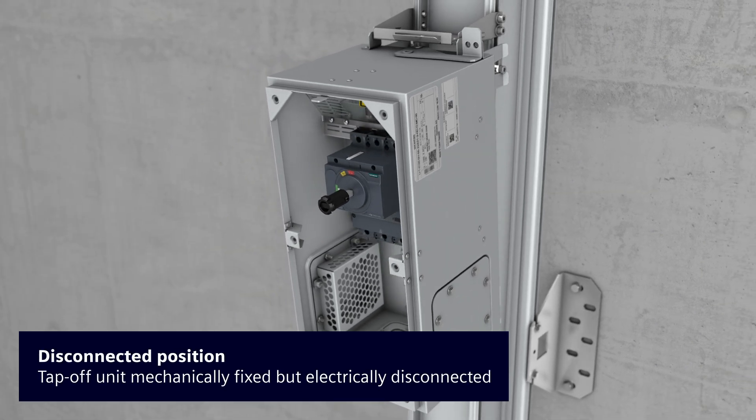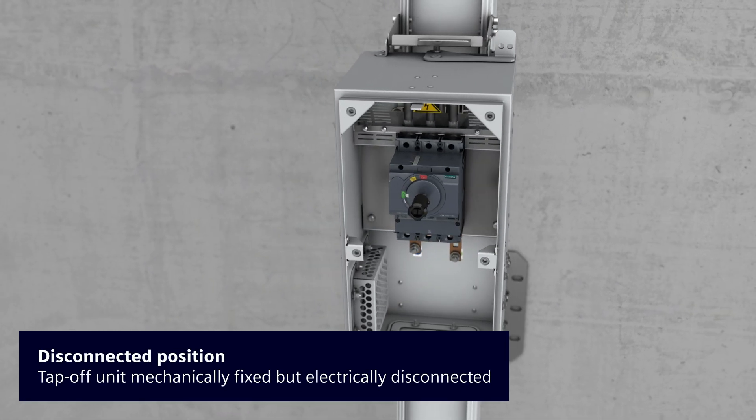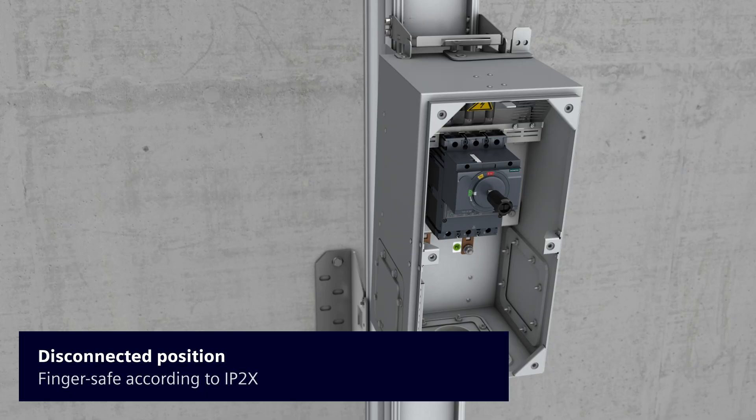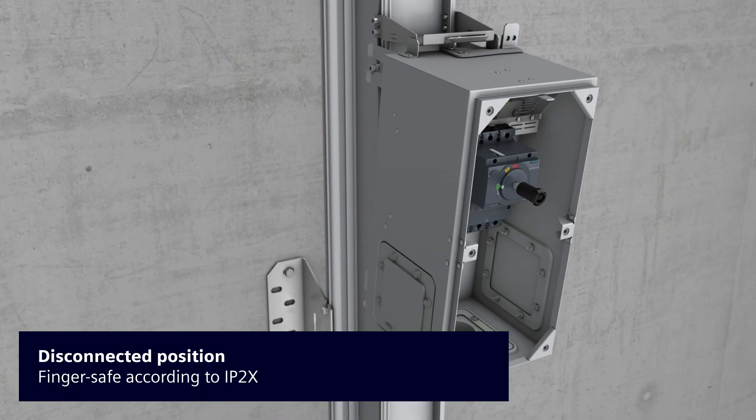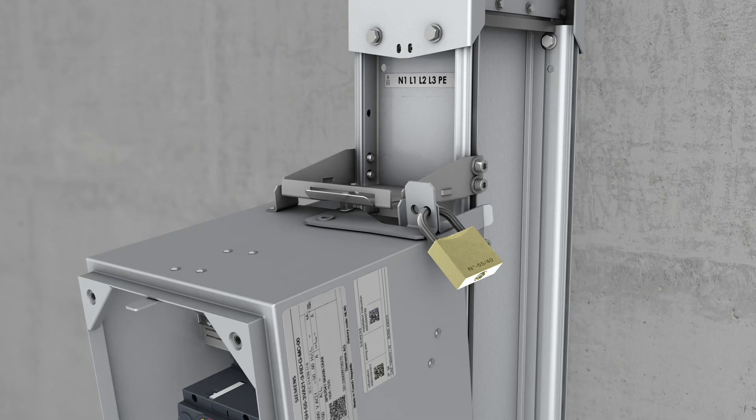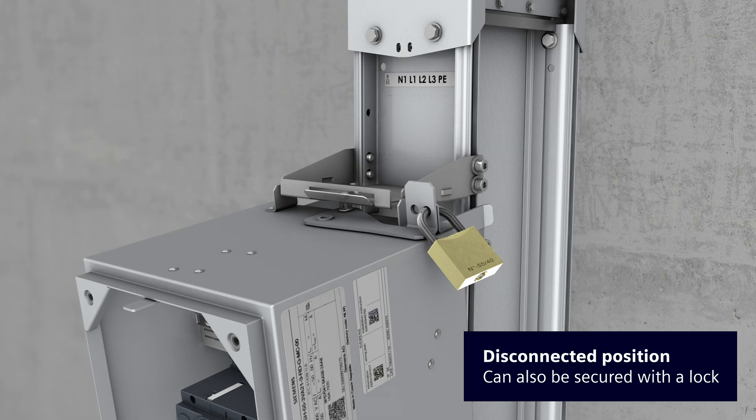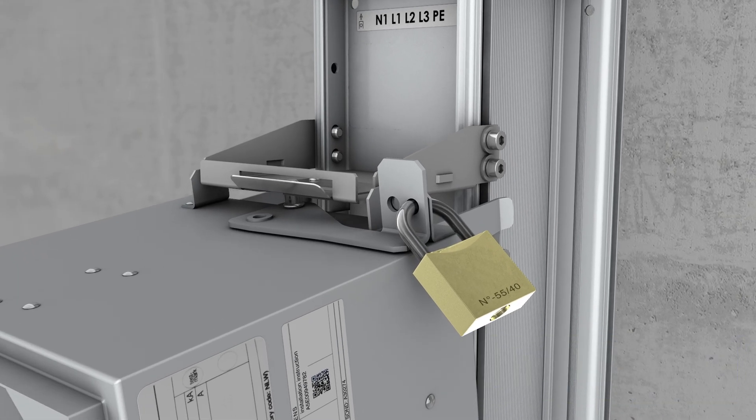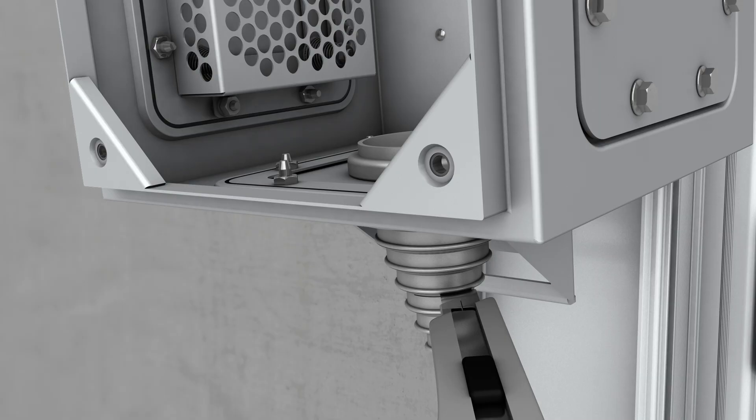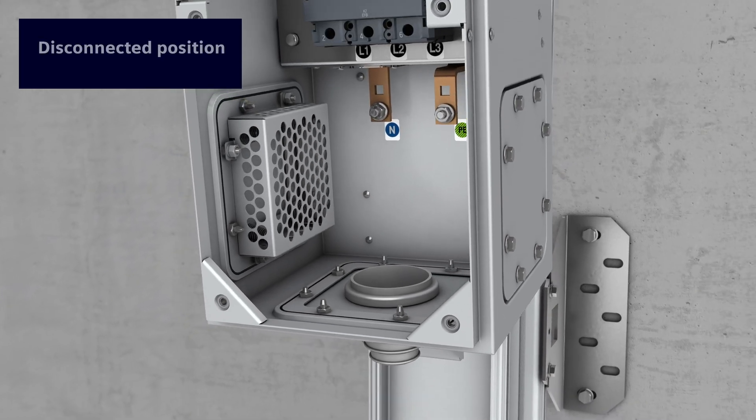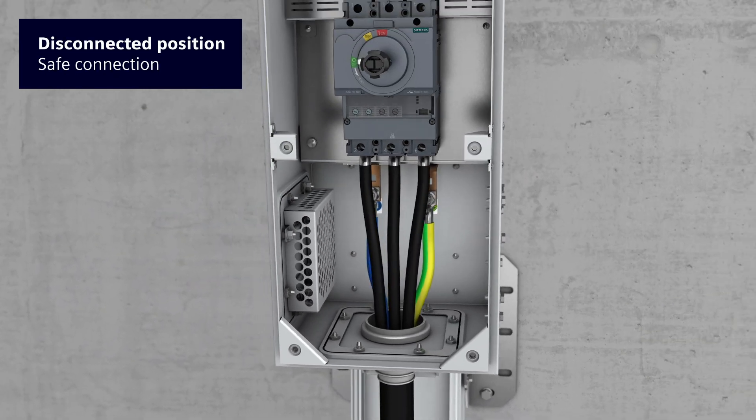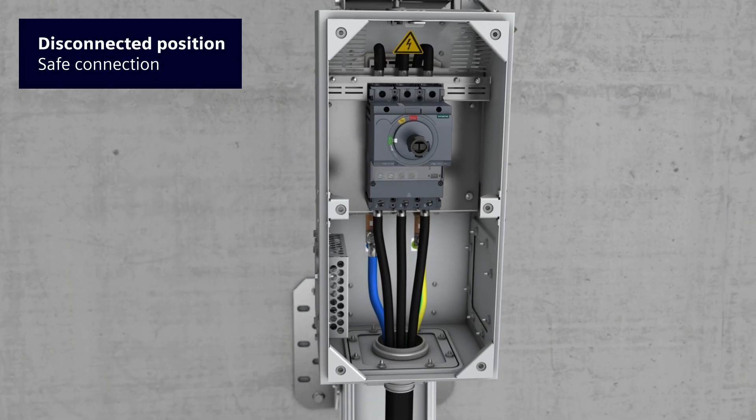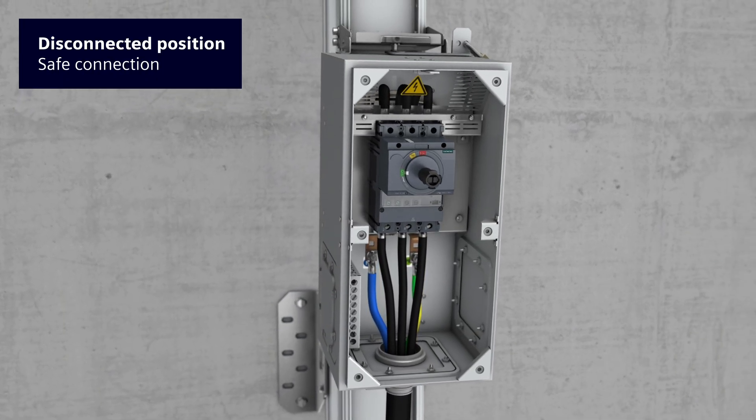The tap-off unit is now mechanically fixed, but is still in disconnected position and is finger-safe in accordance with IP2X. A second safety level can be optionally implemented by adding a lock to secure the retaining lever. The electric connection of the consumer to the tap-off unit can now be carried out safely by simply connecting the consumer cables.